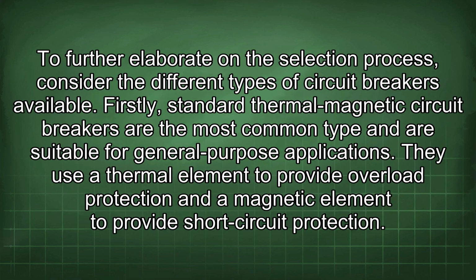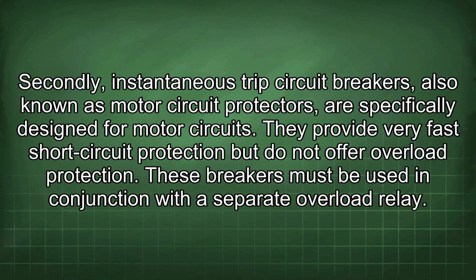To further elaborate on the selection process, consider the different types of circuit breakers available. Firstly, standard thermal magnetic circuit breakers are the most common type and are suitable for general-purpose applications. They use a thermal element to provide overload protection and a magnetic element to provide short-circuit protection. Secondly, instantaneous trip circuit breakers, also known as motor circuit protectors, are specifically designed for motor circuits.